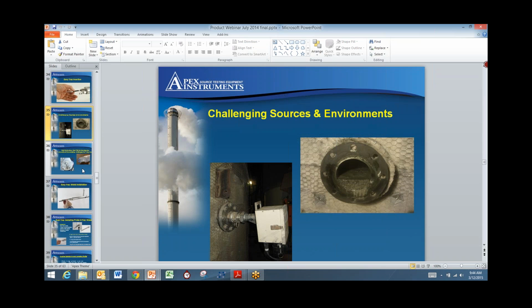For the one we put in the annular space, if the control box were to be mounted in the annular space, how would any leakage of combustion gas into that annular space affect the meter? If it's sucking air out of there that's got combustion gases. The combustion gases as part of the sample are actually vented out of the cabinet after it goes through and is measured, and you can route that out to wherever you need to, window, whatever. As far as the actual gas in the annular space, the air conditioner itself is like a closed loop system, so it's not actually drawing air in from the outside. It just recycles the air in the cabinet, keeps it from a constant exposure to that. If it did become an issue where it was real high or something, I have had people put air to the cabinet and just create a positive pressure.